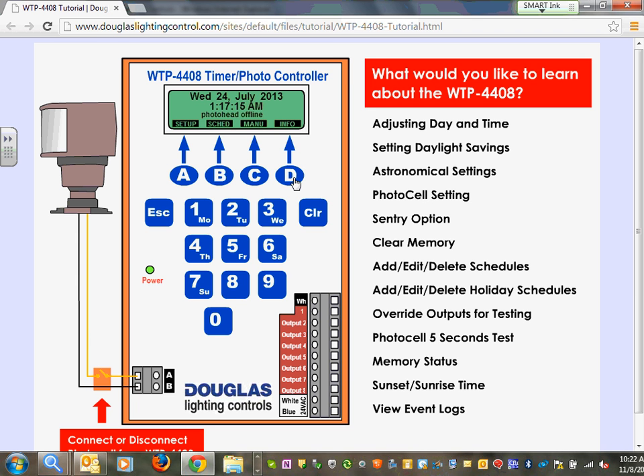But this lets me put this device in, whether it's that light fixture or say I've got a pole mounted light with a photocell on it. I can take the photocell out and put this photocell in. It's got the same unit configuration as the photocell on top. Now without adding control wires, I put this in the photocell of the fixture that's sitting on the parking lot. I can talk to this photocell from the router and tell it what it's supposed to do and when it's supposed to do it. And now I have complete wireless control of all these fixtures.